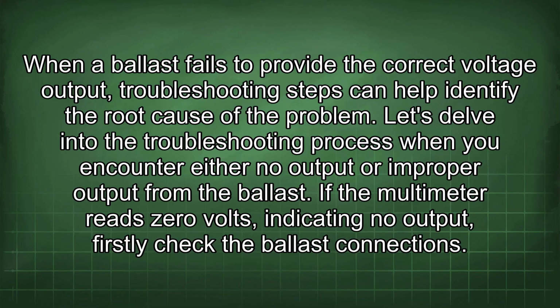When a ballast fails to provide the correct voltage output, troubleshooting steps can help identify the root cause of the problem. Let's delve into the troubleshooting process when you encounter either no output or improper output from the ballast. If the multimeter reads 0 volts, indicating no output, firstly check the ballast connections.